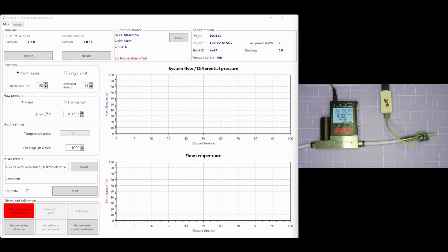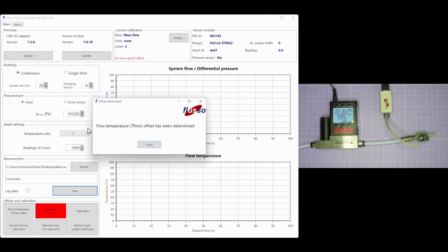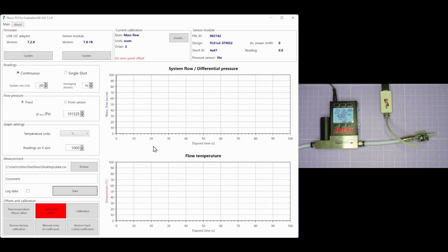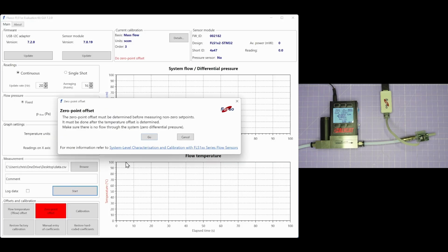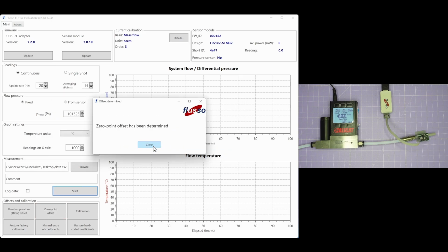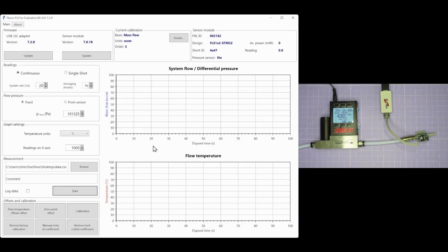Calibrating the FLS1x2 module couldn't be easier, whether you're using the evaluation kit GUI like I am here, or using pure I2C transactions. The process is the same. The first thing you're going to want to do is to make sure there's no flow through the sensor and perform a flow temperature offset calibration. Here you enter the ambient device temperature, which in my case is 24 degrees, and that will determine the T-flow offset correction. Then you're going to want to determine the 0 point correction. So again, with no flow through the sensor, just simply perform a 0 point offset. Once those two procedures are complete, the device is going to have a good measure of 0 point, and so now we can perform a full calibration.